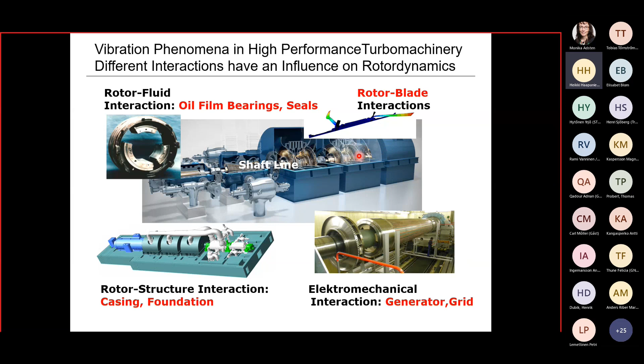Furthermore, and this is known since long, there is also a rotor-structure interaction, for example, with casing, foundation, pedestal, and so on. And we should consider this when we look at lateral vibrations. On the right-hand side, torsional vibrations around the axis. There we have interactions, of course, with the electromechanical system in the generator and in the grid. And there are air gap torques acting in the generator, which excite the rotor shaft line to torsional vibrations. Another effect is the rotor blade interactions, especially in the last stages of the low pressure turbine. So there may be bending of the blades, and this bending of the blades interacts with the torsional vibrations of the shaft line.